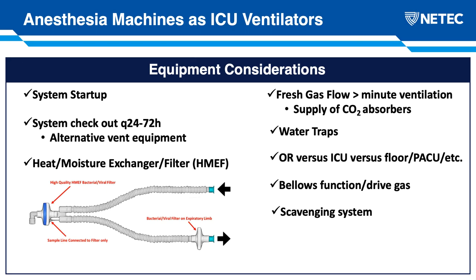For the bellows on an anesthesia machine, some of these are electric. They're driven by electricity, and some of them are driven by high pressure gas being pressed in around the bellows to cause it to drive ventilation of the patient. For those systems that use drive gas that are pneumatic, they all come programmed to use oxygen. And while that is preferred as an added layer of safety in the case of a breakdown in the barrier between the bellows and the outside housing, there is the ability to convert that to compressed air. That would just need to be done by a trained technician if there were ever concern about lack of oxygen availability.